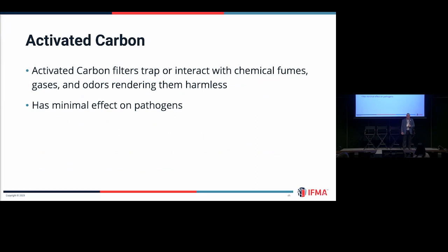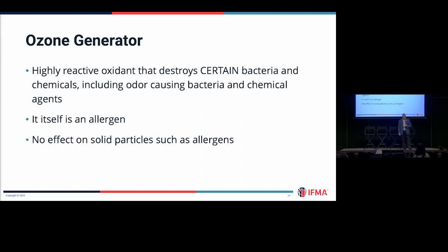Activated carbon, that's been around for a lot of years as well. That too is something where the air has to pass through and capture, but it will basically only capture odors. It cleans smells out of the air, and that's about all. Some viruses will get caught by accident, but it's not designed for that. The filtering medium is not tight enough to catch viruses and pathogens. So it has a minimal effect on those. But if you have odors you need to get rid of, it's the best thing out there.